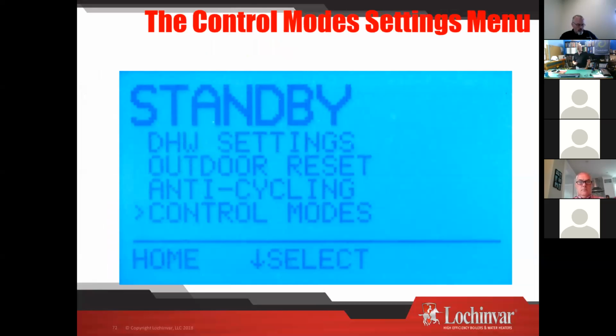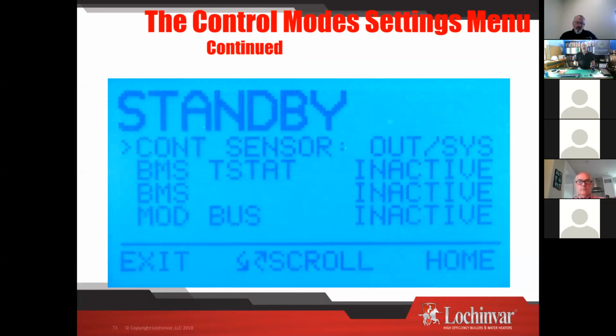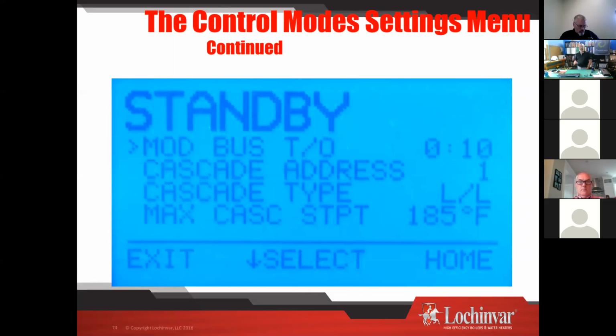All right. Control modes, not going to spend a bunch of time here, just really let you know that they're there. But this is really where we're going to get into talking about in the control BMS. Residentially, one of the times we'll use this is if you're using some sort of external indoor feedback control, Tekmar indoor feedback or Tekmar's room response control, where it's feeding back to the boiler, giving it a design water temperature. You can also connect it to a building management system. So our 50,000 BTU boiler has all the same abilities as our 6 million BTU boiler when it comes to this BMS communication and stuff like that. So if you want to put a full BMS system inside your house and connect to your boiler, it'll do it. It'll communicate to it. All of that's going to be in there.